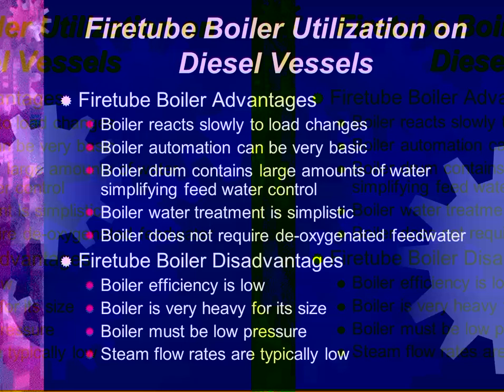Because it is low pressure, boiler water treatment is simplistic and it does not require deoxygenated feed water. Once you get above about 600 pounds, your boiler water treatment is starting to get much more complex and you start requiring a DC heater and a closed feed system.